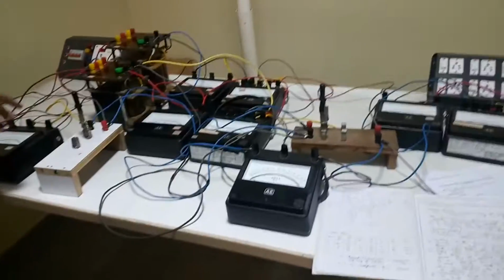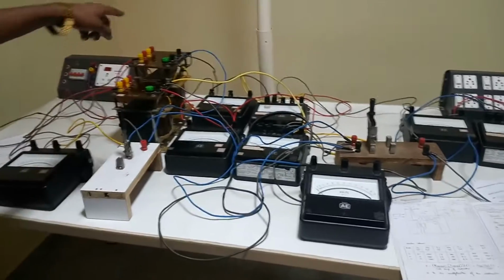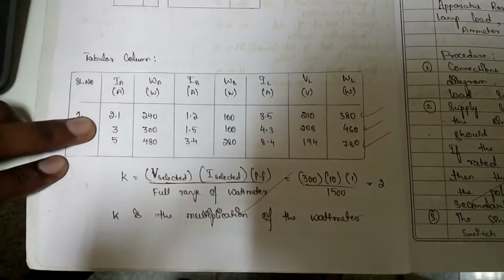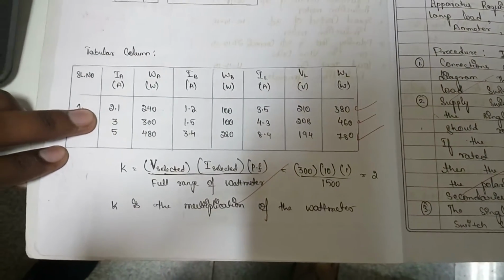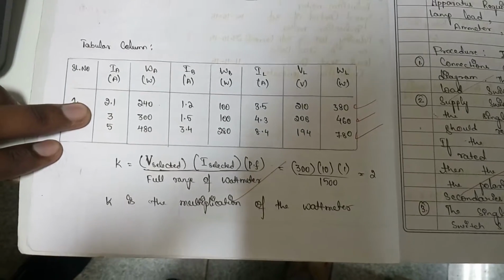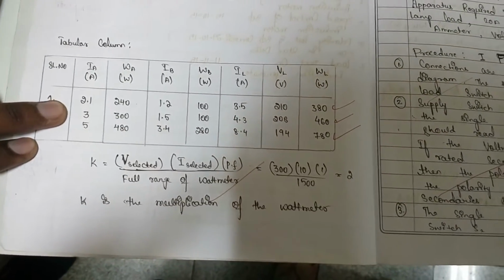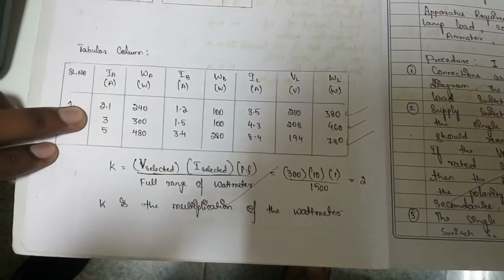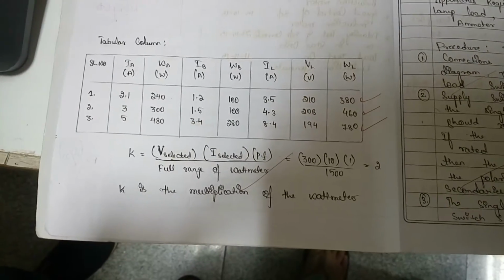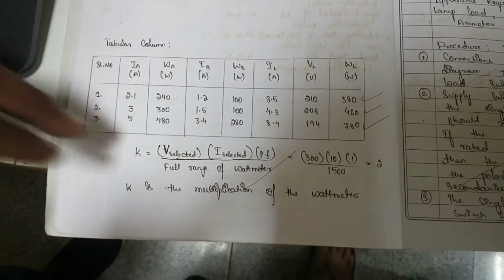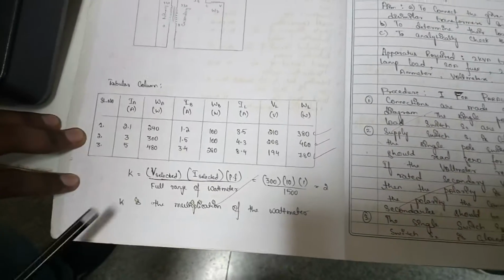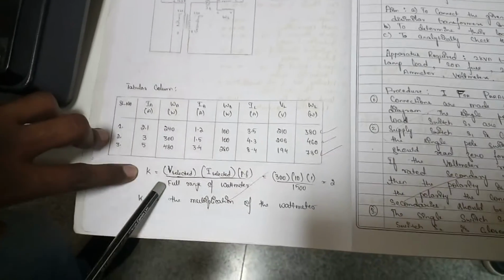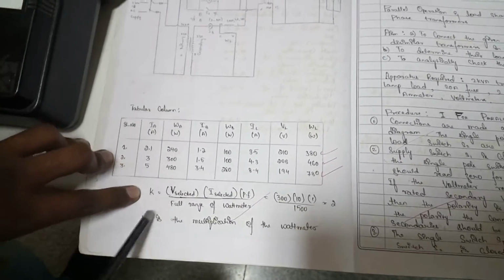Now we will be finding out the kVA ratings of that one. So we will be finding out the I rated of these two transformers, and within the range only we need to take the readings. We will take the first reading from approximately 2.1. You can take any between the ranges of 2 to 8 amperes, because 2.4 is the I rated for the 1 kVA transformer, and 8.9 is the I rated for the other transformer. So your readings should range between 2 amperes to 8 amperes. You can take 3 readings, or more than 3 readings. We will be calculating K. This is the wattmeter constant, which needs to be multiplied with the wattmeter readings.